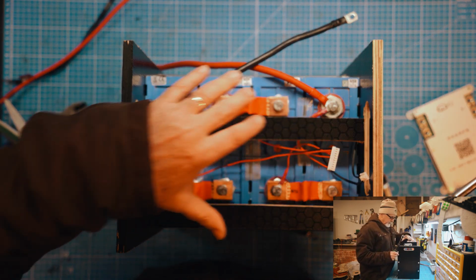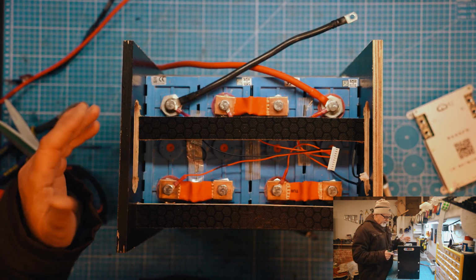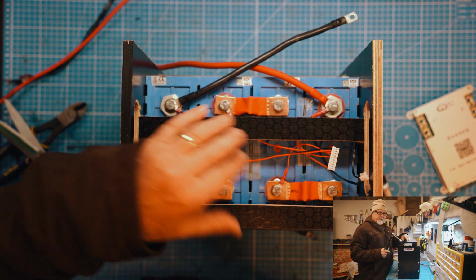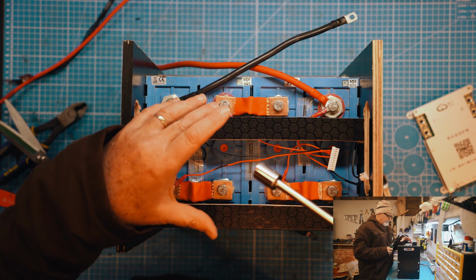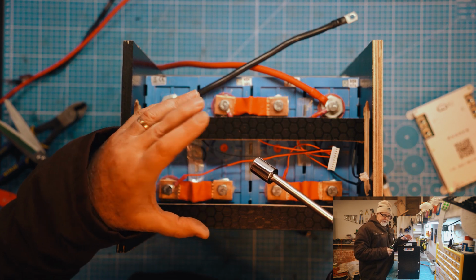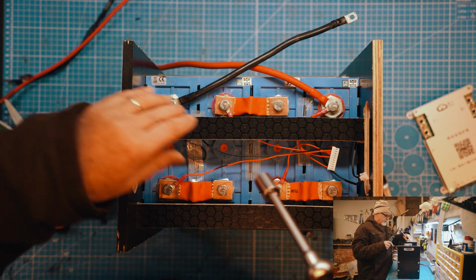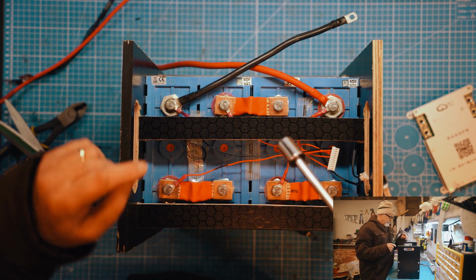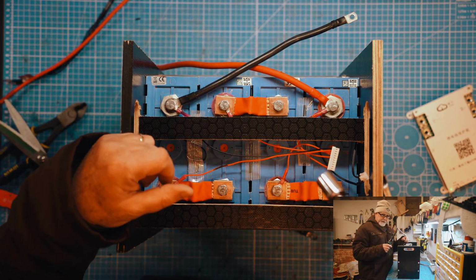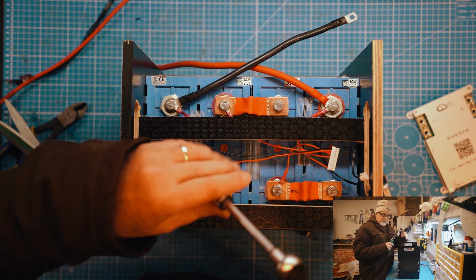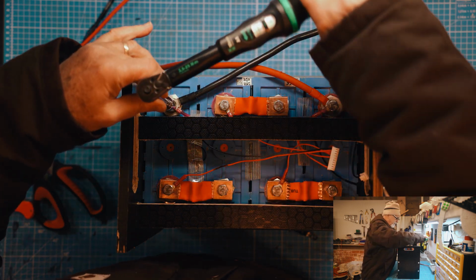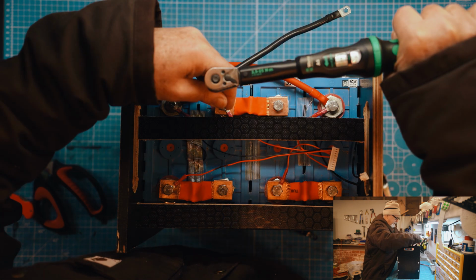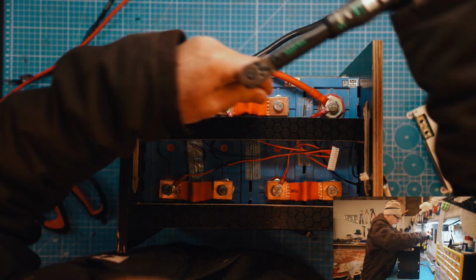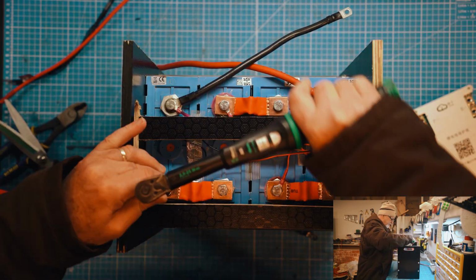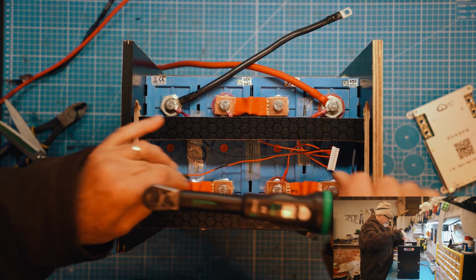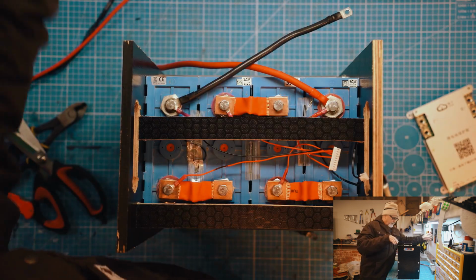Before I mount the BMS onto these bars, I'm going to do one last tighten. Always good to run through everything at least once again, if not twice, to make sure that you haven't left anything undone. If there are any that are finger tight by mistake that you haven't tightened up, you're going to have arcing, you can have all sorts of problems. So always a good idea to run through everything and do it in whatever logical sequence you'd like to work with, but just make sure you get to each one, you don't skip any out. That's it, they're all tightened.